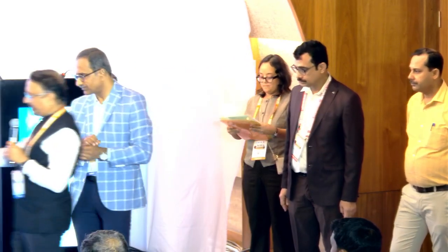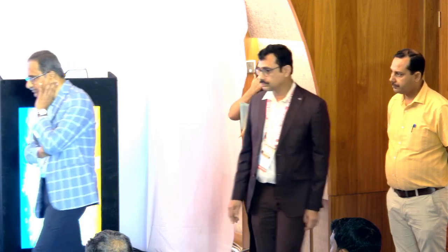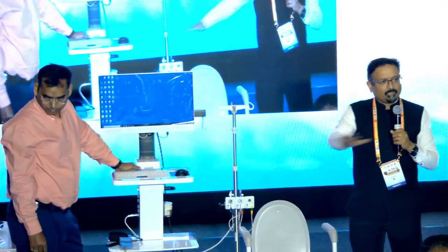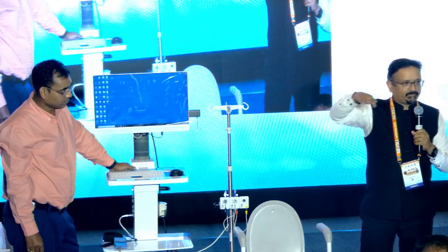Now here you have to understand that there are a lot of errors and artifacts that can happen, which you can actually correct only when you are there in the room. For example, if there is an air bubble in the filling lumen of the double-lumen catheter, the filling will clear that. But if it is in the lumen where you measure the detrusor, the vesical pressure, it will give you a false reading. Similarly, this is a transducer here. This transducer also has to be completely filled from below, and then it should be emptied of all air bubbles. If there is any air bubble, you will not have a proper recording.